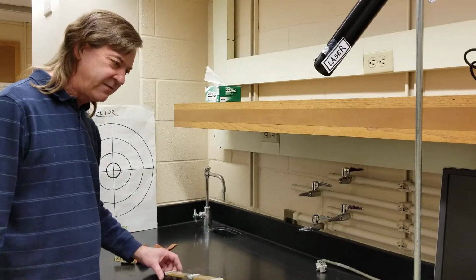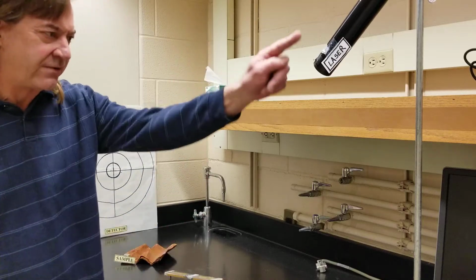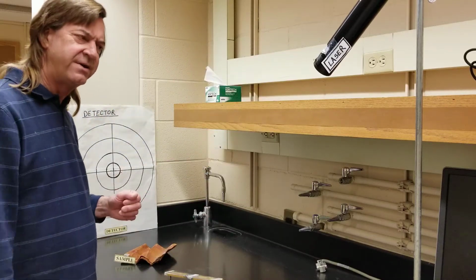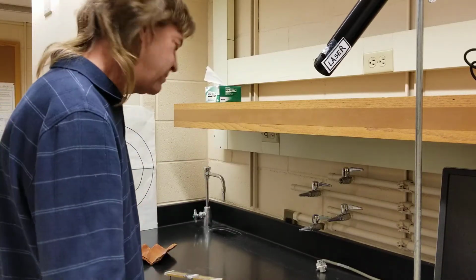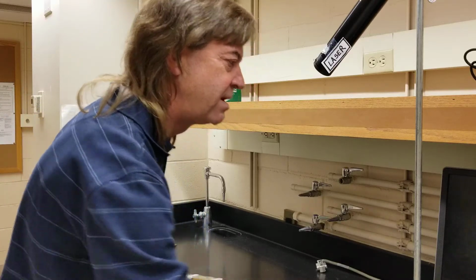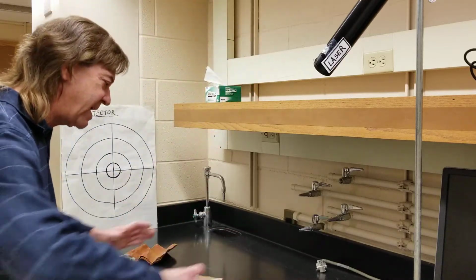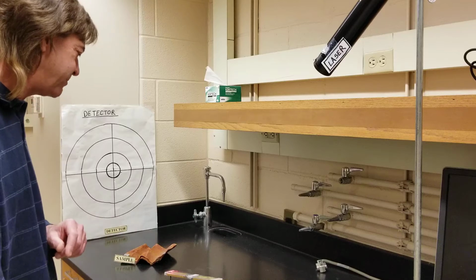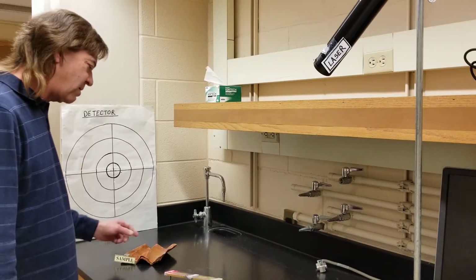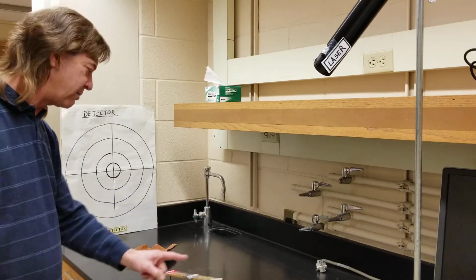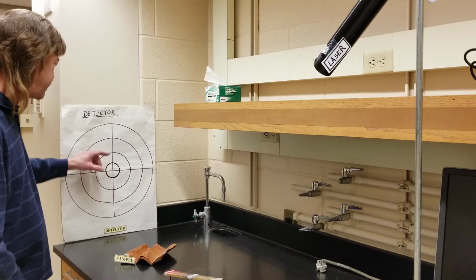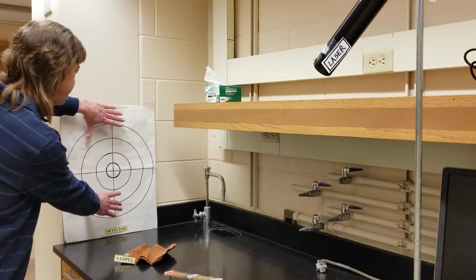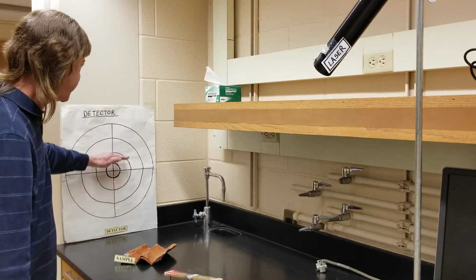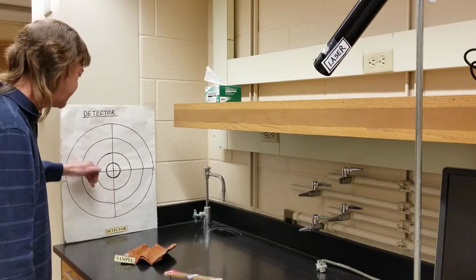Anyway, the cantilever is right here. The laser is going to bounce off it. And the first thing we need to do is actually line up the laser. You go ahead and turn the laser on, and then move the cantilever until the laser hits it at the tip. Oh, there we are. Now, once it does that, you'll see how it reflects and goes onto our detector. This is our photodiode detector. It knows where the light's hitting it, as far as up or down, left and right.